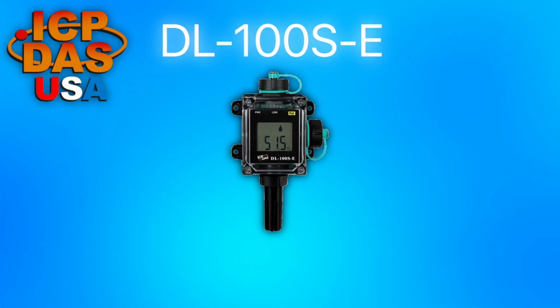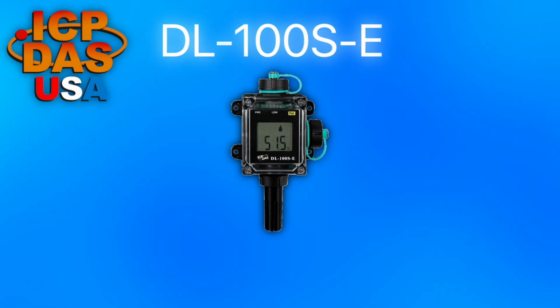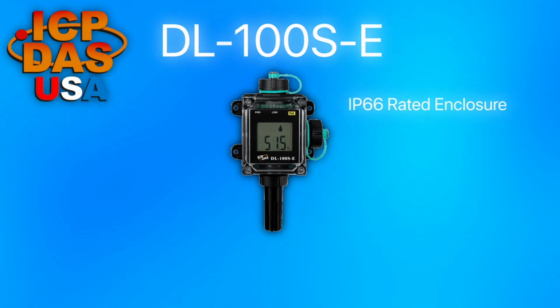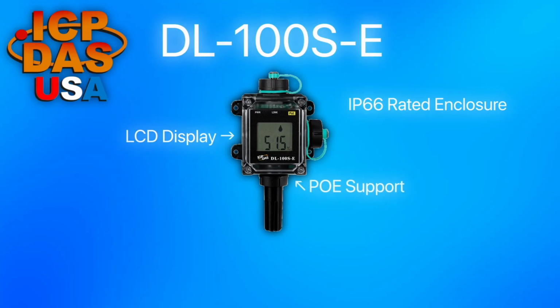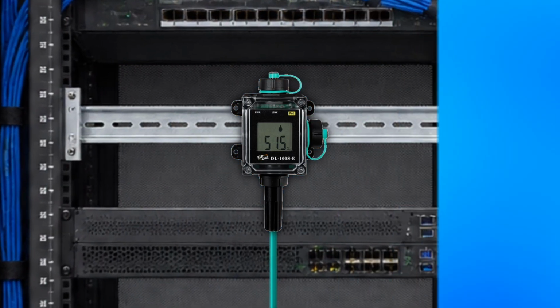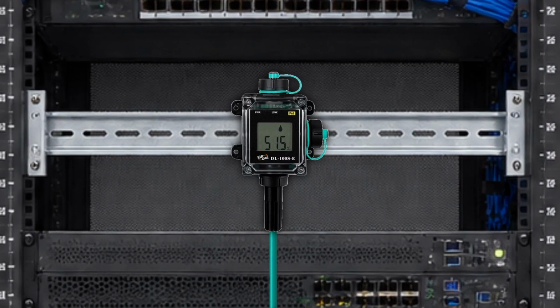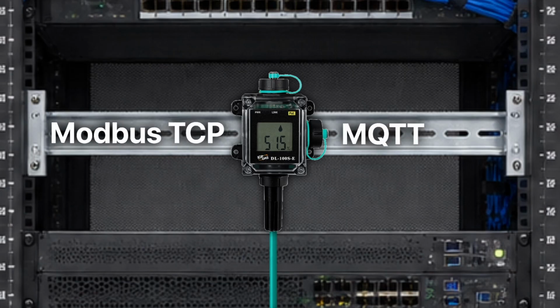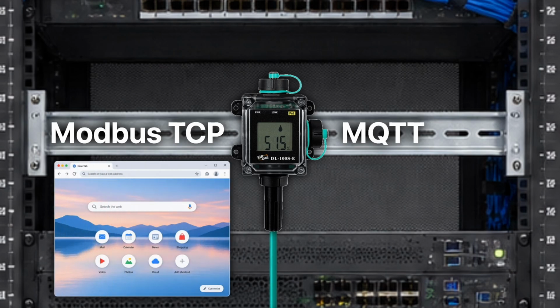It's the ICP DAS USA's DL-100S-E. It's a compact temperature and humidity data logger designed for exactly this kind of distributed monitoring. It has an IP66 rated enclosure, a built-in LCD display, and PoE support, which means it powers and communicates over a single Ethernet cable with no separate power wiring required. You simply mount it where the risk is, and it immediately starts logging temperature, humidity, and dew point with a timestamp on every record. You can use either Modbus TCP or MQTT for integration into whatever monitoring infrastructure you already have, and you also get real-time data that's accessible through a web browser or the free mobile app from anywhere on the network.